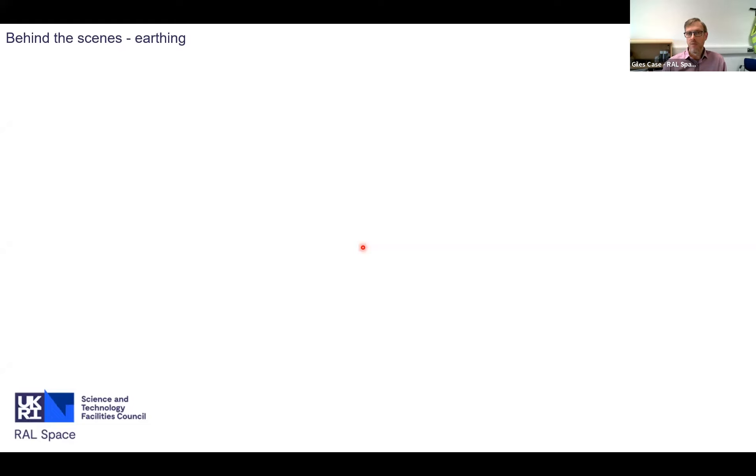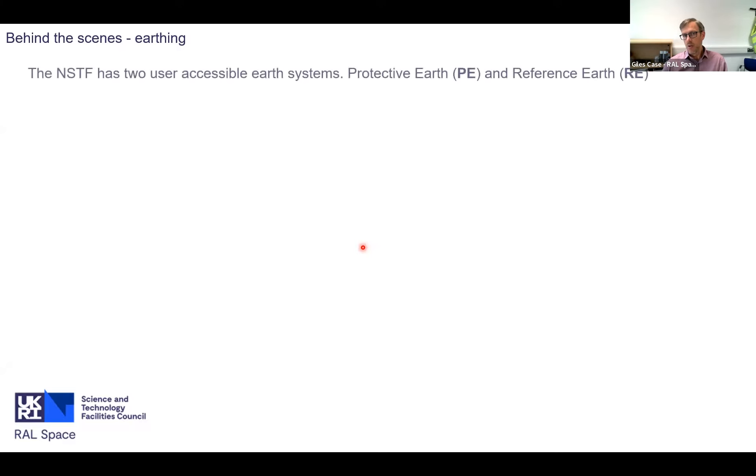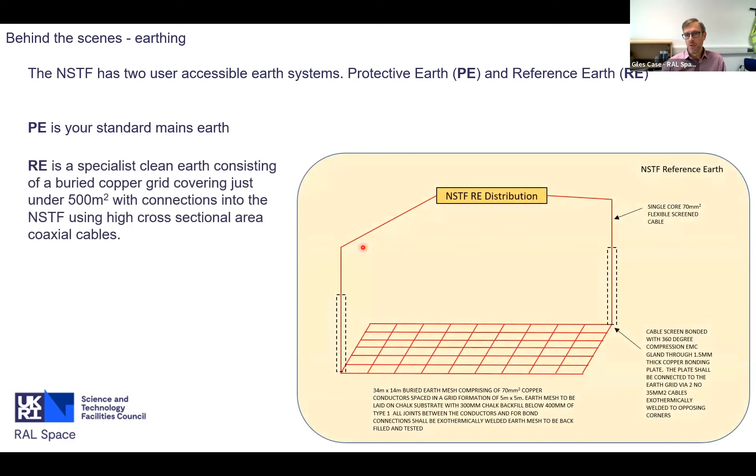Another important part of the big infrastructure items is earthing. The NSTF has two user earth systems: protective earth and reference earth. Protective earth is standard mains earth - the thing that's there for electrical safety. The reference earth is, in our case, about a 500 square metre copper grid buried underground, connected into the building using high cross-sectional area cables of about 70 millimetres squared. It's buried under our rainwater attenuation system so it can't be easily disturbed, and there's a road on top of it as further protection.